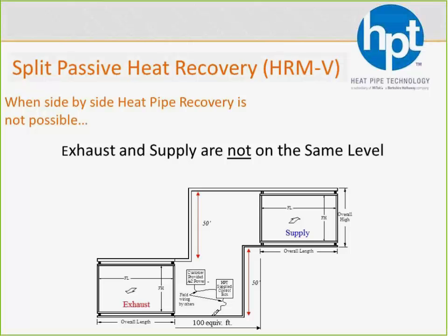The only downside to this is that we're only going to work in one season now, because that liquid is only going to go down. So you want that warmer airstream at the bottom to take that liquid and boil it so that vapor goes up, and then when it condenses after giving off that heat, that liquid can only go downhill. So typically, the majority of the time you're going to want heating season recovery, so you'll want that exhaust airstream to be at the bottom to get your best bang for the buck.